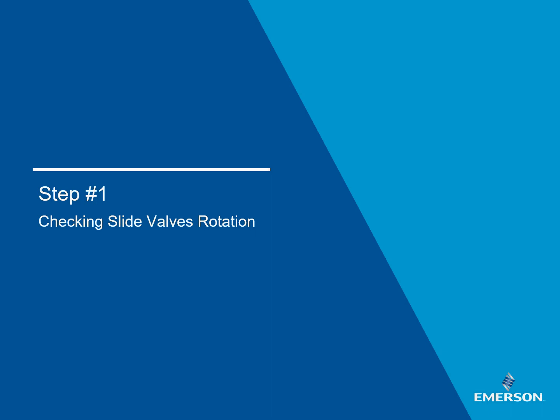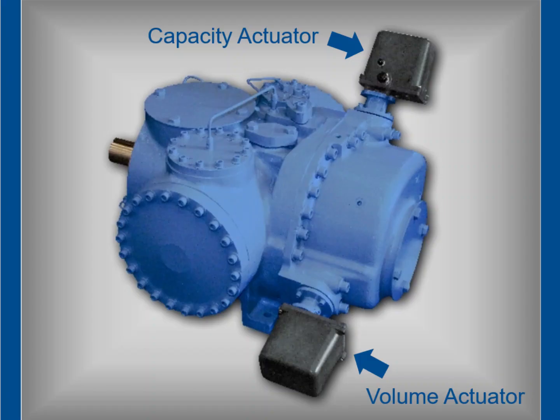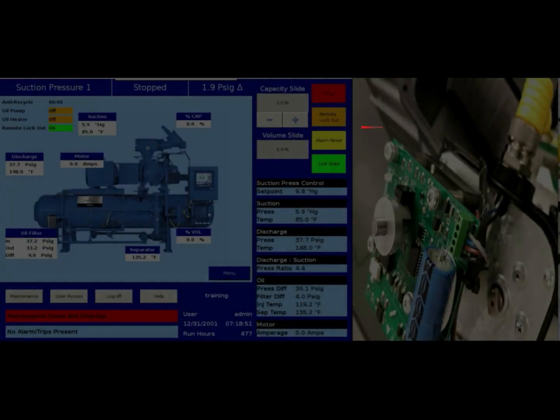Before starting actuator calibration, we want to identify the location of our capacity and volume actuators. The capacity actuator is mounted on the upper side, and the volume actuator is mounted on the lower side of the compressor. You can see the same orientation on the slide valve calibration screen.